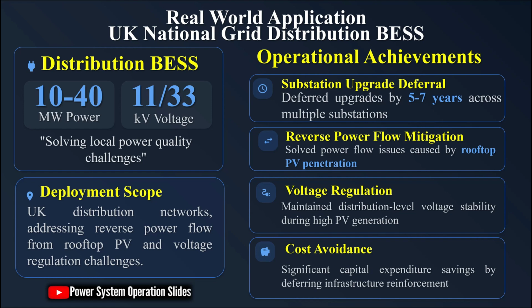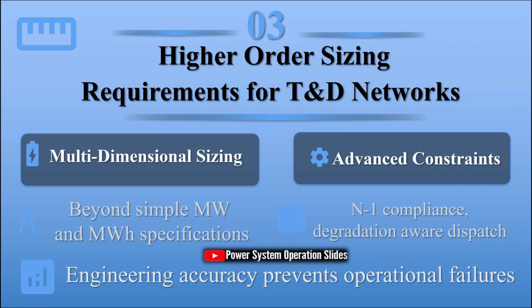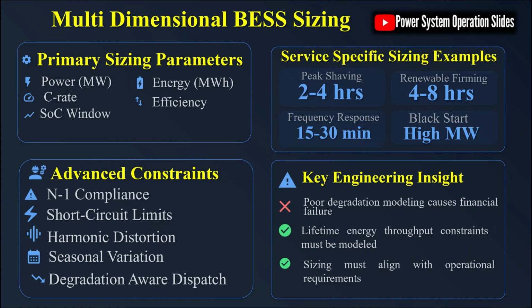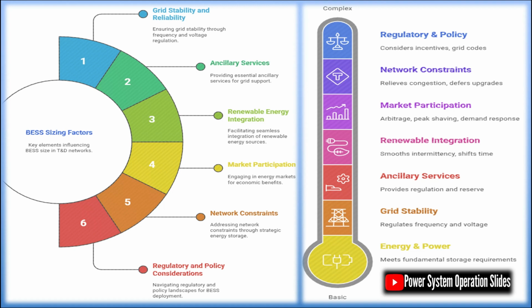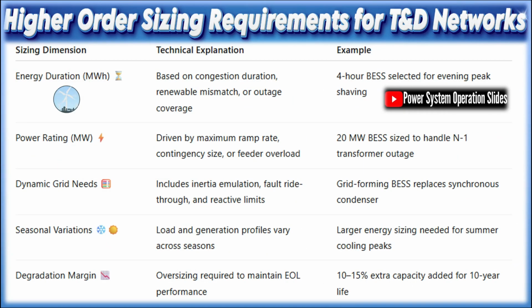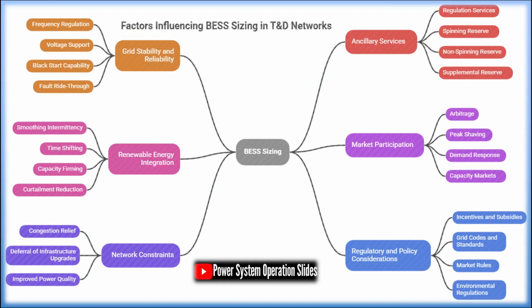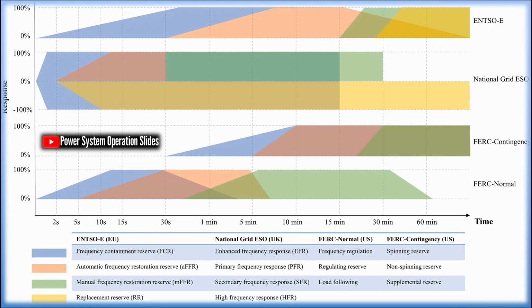Voltage regulation through reactive power control, QV control, allows BESS to inject or absorb reactive power to maintain voltage levels within acceptable limits, particularly at the distribution level where voltage fluctuations caused by distributed generation can be problematic. Congestion relief without network reinforcement represents another critical BESS function. By storing energy when transmission constraints would otherwise limit power flow and discharging it when constraints are relieved, BESS can defer expensive transmission upgrades and improve overall grid utilization. Finally, islanding and black start support capabilities enable BESS to maintain operation of critical loads during system disturbances and assist in system restoration following blackouts, a capability that becomes increasingly valuable as the grid's resilience requirements become more stringent.